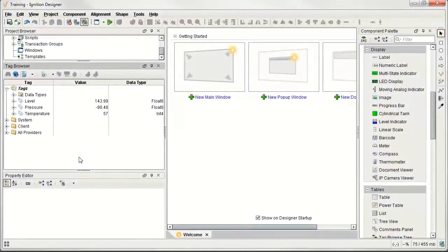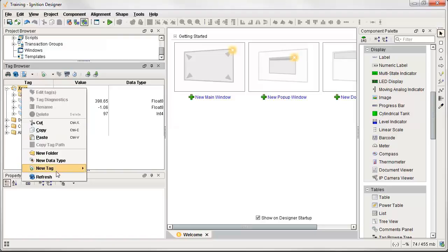The next scan class we're going to create is another driven scan class where the operator can control the rate at which we poll the PLC by simply writing to a trigger value. So it's very similar to the previous scan class we created where we're looking at the machines on or off. But rather than getting the value of the trigger from the PLC, we're going to get the trigger from Ignition. And we're going to do that by creating, in the Designer, a memory tag.